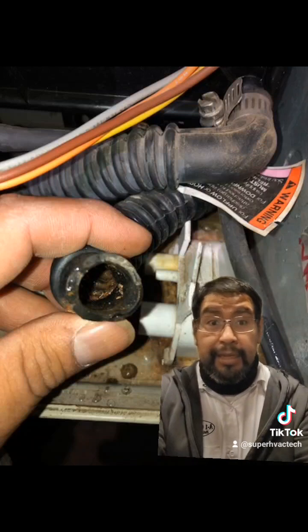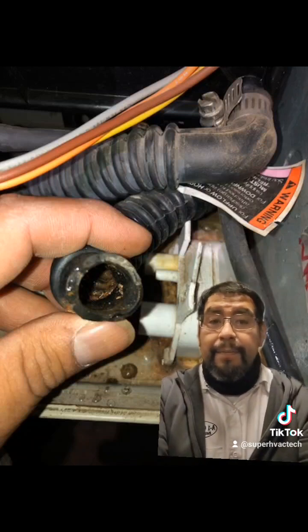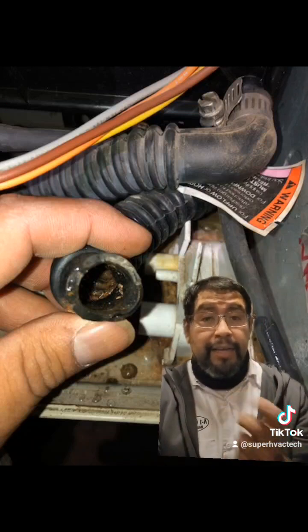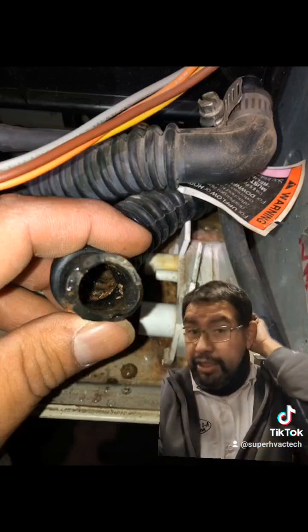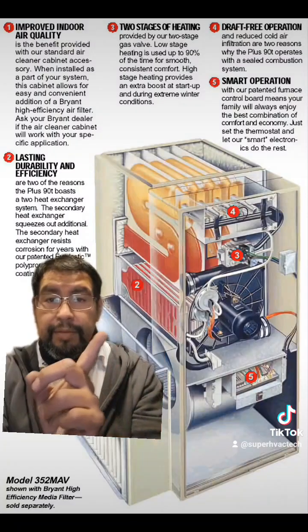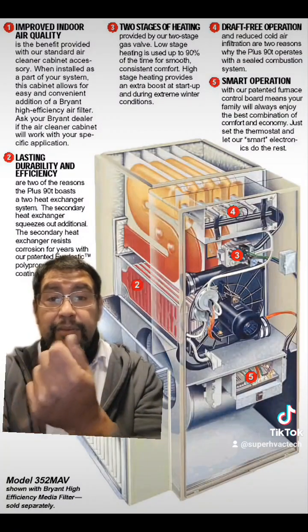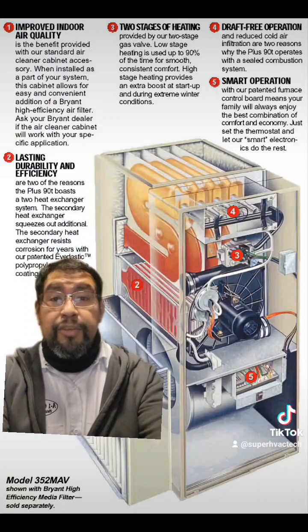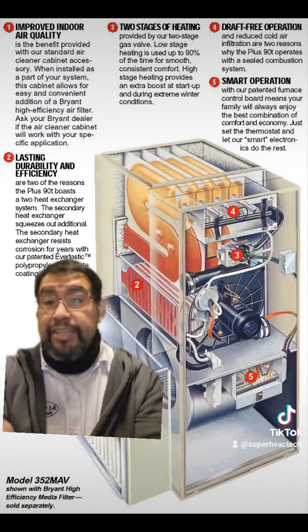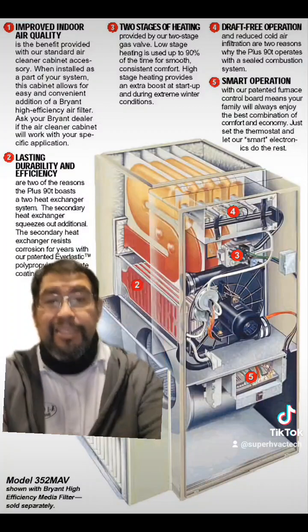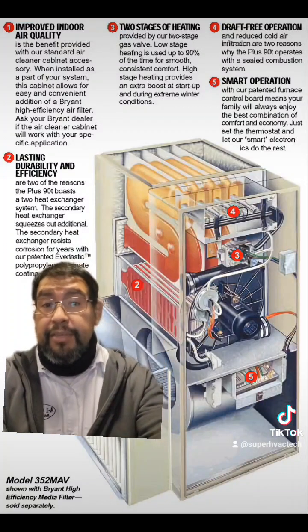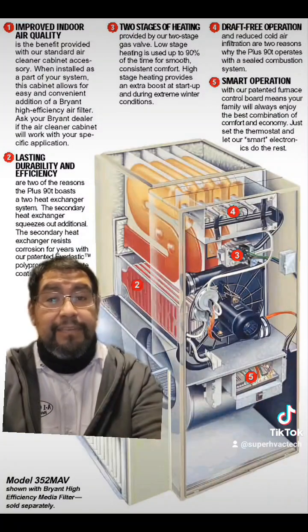If you have a really high temperature rise, or if you take the blower out and you can look at the secondary heat exchanger right there, and you can see actual water and corrosion coming out from there, that's your sign that the heat exchanger is bad. Due to the age, it might be better to just replace the unit. So stay safe out there, you guys.